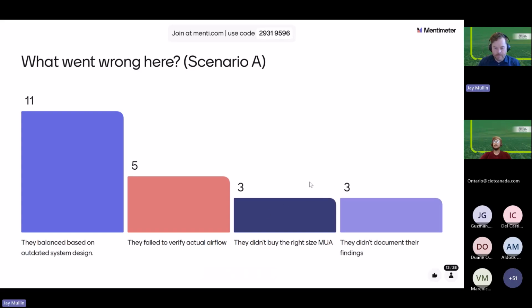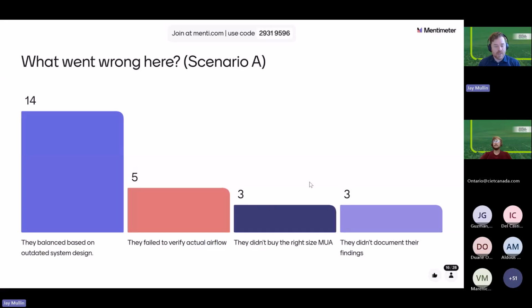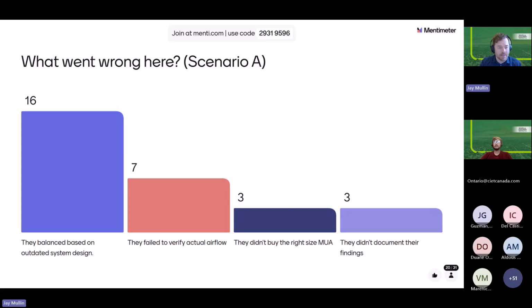All right. Yeah, so some are saying they didn't buy the right sized makeup air unit. That could be correct. They didn't document their findings. That's also correct, that's good practice. They didn't do that, but I think what this one's pointing to is they balanced based on old system designs, and they didn't verify actual airflows. So with these first 2 options, they did that desk evaluation, they looked at the facility drawings, they looked at the spec sheets for their equipment, and came to their conclusions based on that without verifying on the ground what was actually happening. So it's a really important step to not just trust what is on paper.